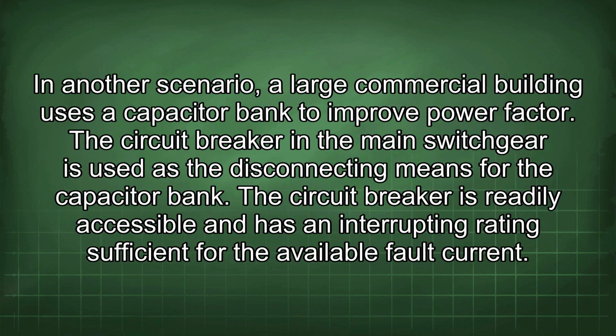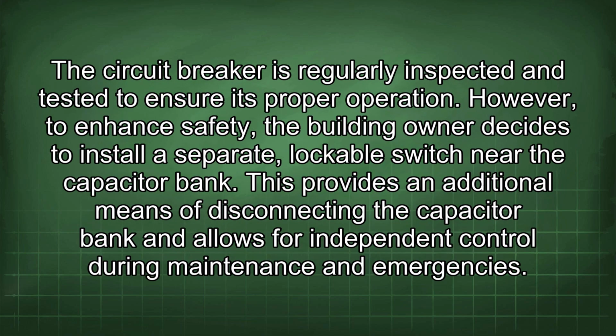In another scenario, a large commercial building uses a capacitor bank to improve power factor. The circuit breaker in the main switchgear is used as the disconnecting means for the capacitor bank. The circuit breaker is readily accessible and has an interrupting rating sufficient for the available fault current. The circuit breaker is regularly inspected and tested to ensure its proper operation. However, to enhance safety, the building owner decides to install a separate, lockable switch near the capacitor bank. This provides an additional means of disconnecting the capacitor bank and allows for independent control during maintenance and emergencies.